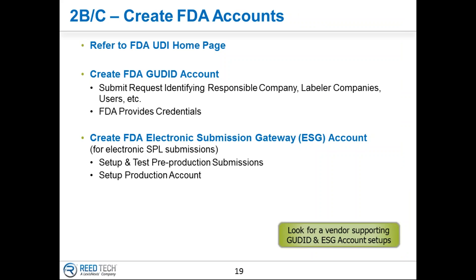After you have a system targeted, the next major step is to create your FDA accounts. All labelers submitting data need to create an FDA GUDID account, submit information about your company and users, and the FDA responds with credentials. You can then work in draft mode and start submitting data electronically or through the website. Those labelers using electronic submissions would also need to set up an FDA electronic submission gateway, which includes a test submission and then creating a production account.